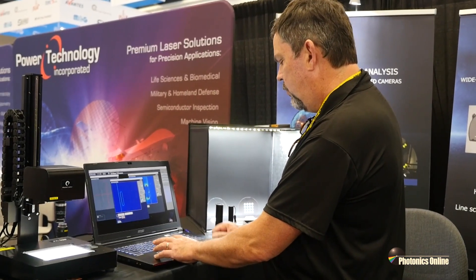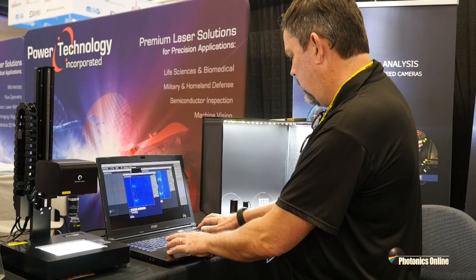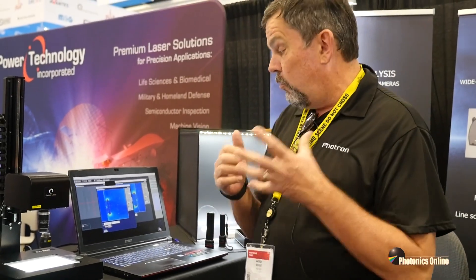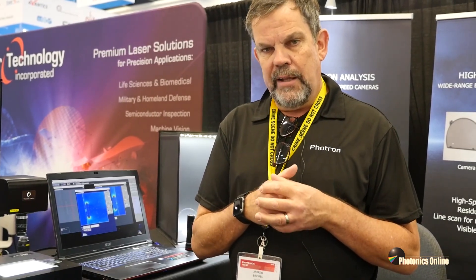When we first come up, it automatically defaults to, in this case, 20. Let's come down a little lower than that — 4. Let's go down to 2. So now we're looking at 2 nanometers of retardance, so very low levels of birefringent residual stress that's left in this iPhone glass cover.